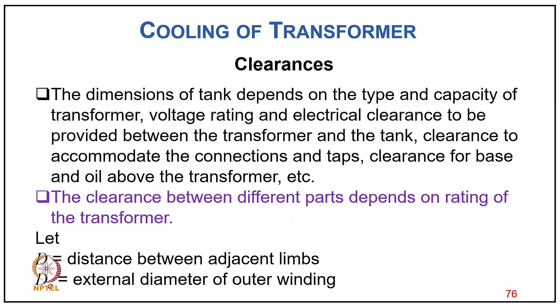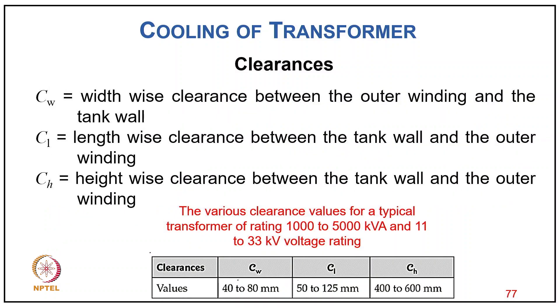The dimensions of the tank depend on type and capacity of transformer, voltage rating, electrical clearance between transformer and tank, and clearance for connections, taps, oil, and base. Width-wise clearance CW between outer winding and tank wall, length-wise clearance CLE, and height-wise clearance CH. For transformers of 1000–5000 kVA at 11–33 kV: CW = 40–80 mm, CLE = 50–125 mm, and CH = 400–600 mm (including 50–60 mm base, 150–250 mm above oil, and 200–250 mm for leads).